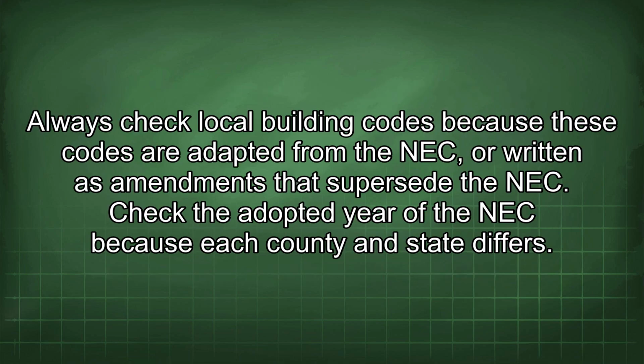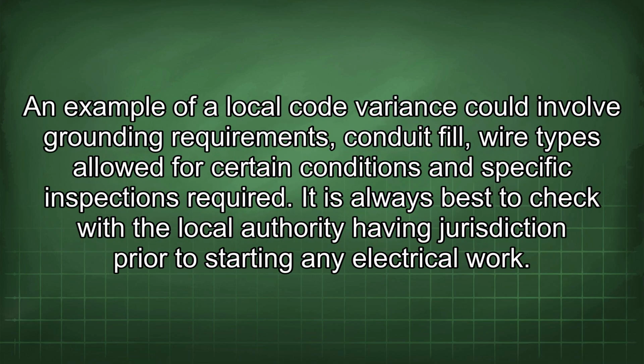Always check local building codes because these codes are adapted from the NEC or written as amendments that supersede the NEC. Check the adopted year of the NEC because each county and state differs. An example of a local code variance could involve grounding requirements, conduit fill, wire types allowed for certain conditions, and specific inspections required. It is always best to check with the local authority having jurisdiction prior to starting any electrical work.